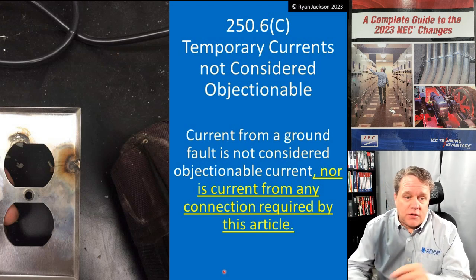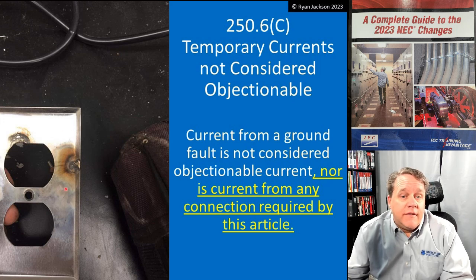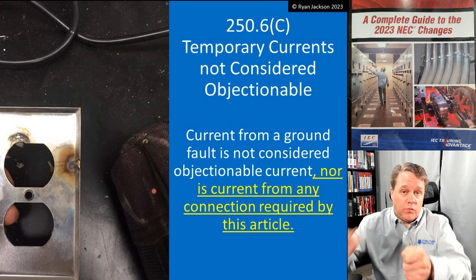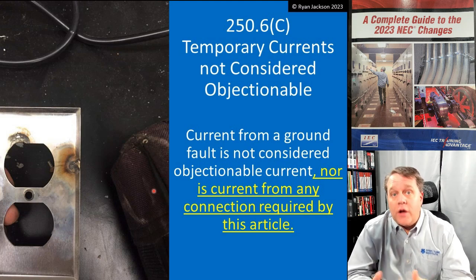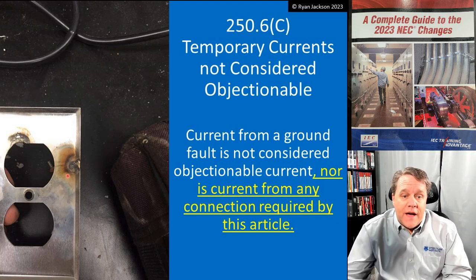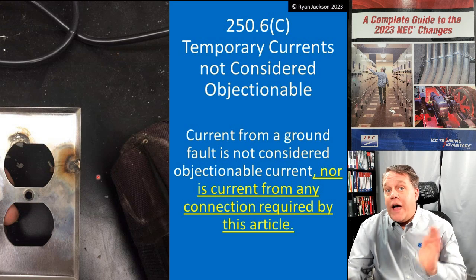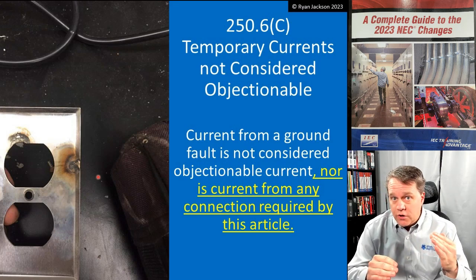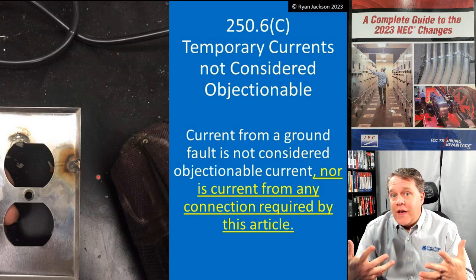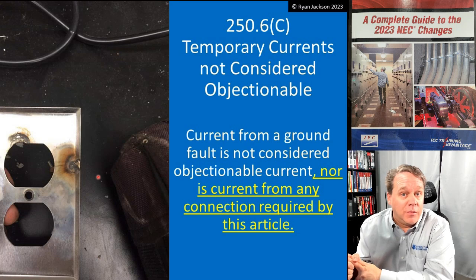Current from a ground fault is not considered objectionable. Here we energized a metal faceplate with a hot conductor, and the arcing and welding on it is actually evidence of a code-compliant installation. During that ground fault, hundreds or maybe thousands of amps of current flowed on the equipment grounding conductor and opened the circuit breaker. That arc is proof we had a low-impedance fault current path to trip the breaker and remove dangerous voltage. That type of current is the equipment grounding conductor doing exactly what it's supposed to do.